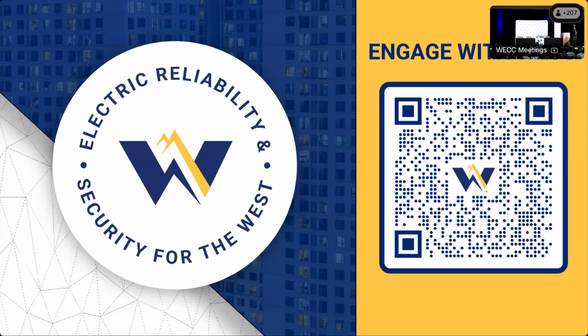Some of your generator operators may be asking this too. It's really weird. We've had many BAs where the graphics I showed were made by a BA engineer because operators were complaining that much. One utility in the West has frequency responsive reserves in a condensing hydro unit. Condensing means no water running through it, the turbine housing evacuated, and the unit is ready to go instantly. They have frequency controls that turn the unit on almost instantaneously, and they were seeing it turn on about three times a day because it was meeting the frequency deviation trigger event.